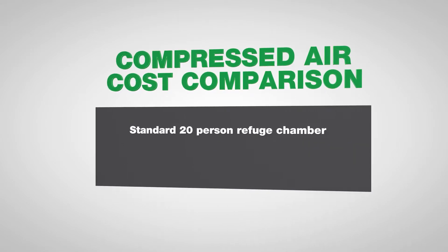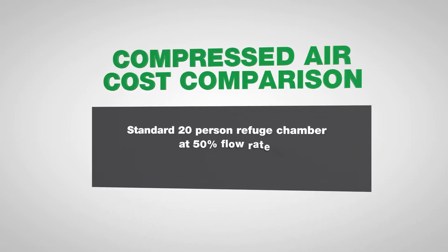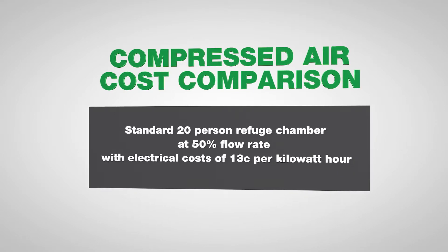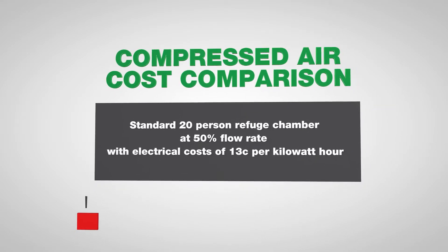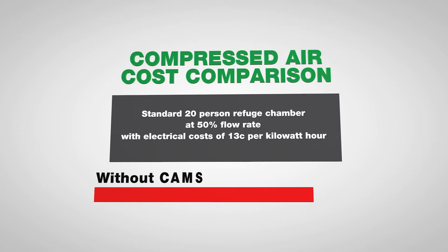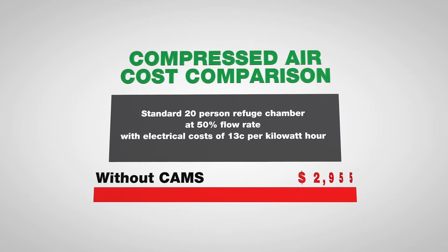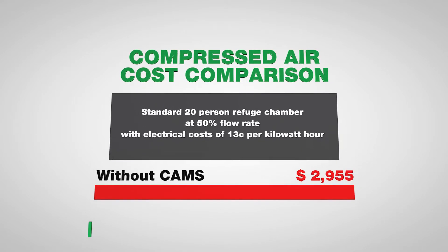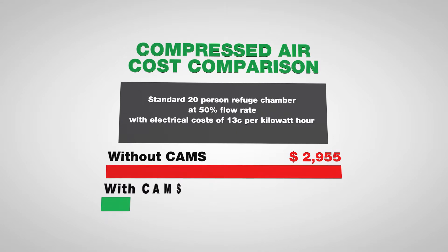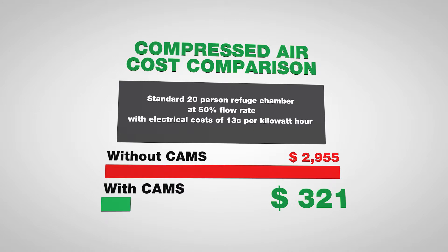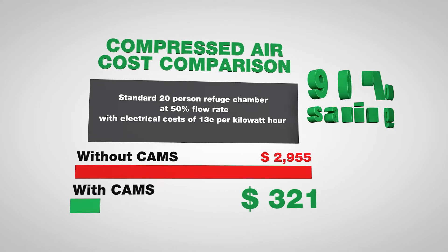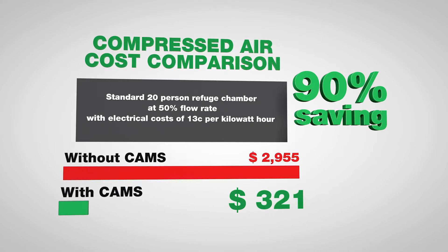For example, a standard 20-person refuge chamber operating at a 50% flow rate and with an electrical cost of 13 cents per kilowatt hour can see a cost of $2,955 per annum. With the use of CAMS, this same chamber's running costs would be reduced to $321, resulting in an impressive 90% savings.